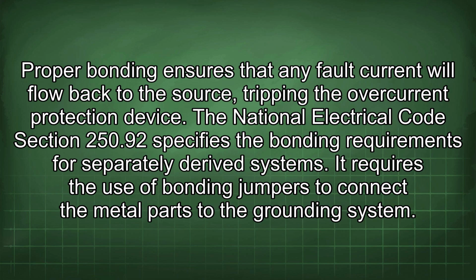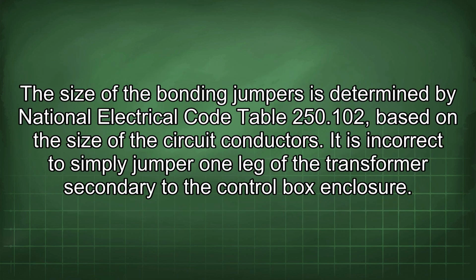The National Electrical Code Section 250.92 specifies the bonding requirements for separately derived systems. It requires the use of bonding jumpers to connect the metal parts to the grounding system. The size of the bonding jumpers is determined by National Electrical Code Table 250.102 based on the size of the circuit conductors.